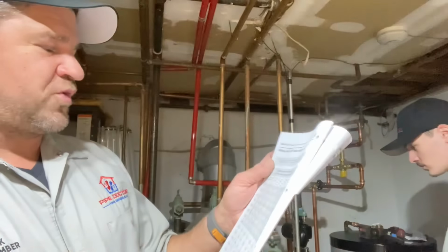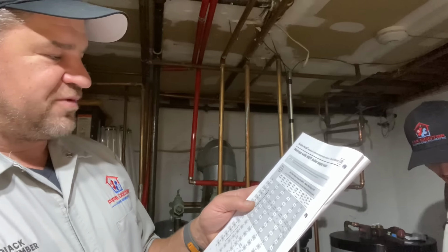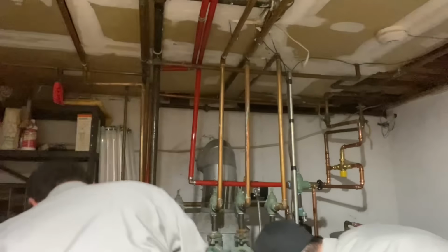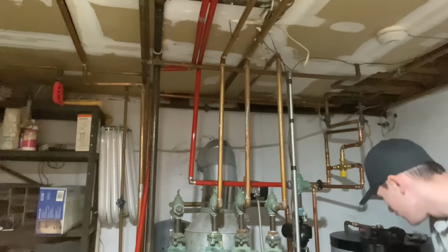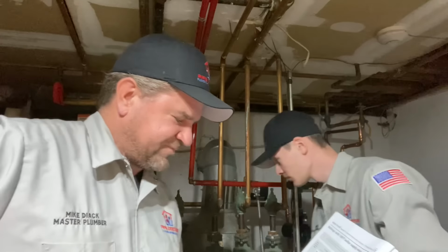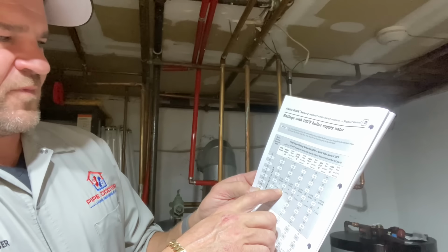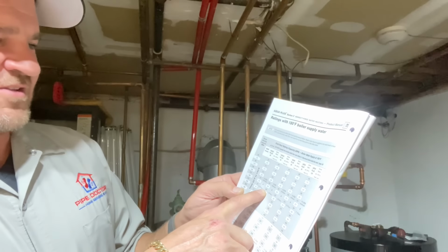All right, but let's real quickly review. We have the Aqua Plus 45. We have a boiler heating capacity. What's the BTUs of this boiler? This boiler is a 7 section. This is a 210,000 BTU boiler. So we're going to go to 210 right there. We're going to go to the Aqua Plus 45, right? And boiler water supply at 180 degrees. I'm going to get 200 gallons. Is that really 200 gallons?